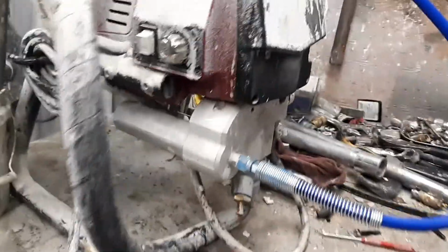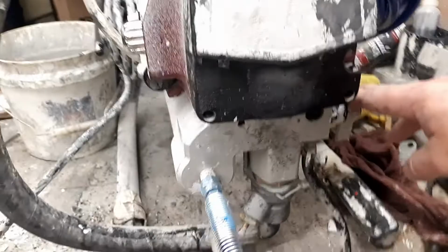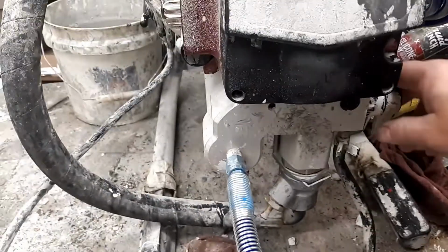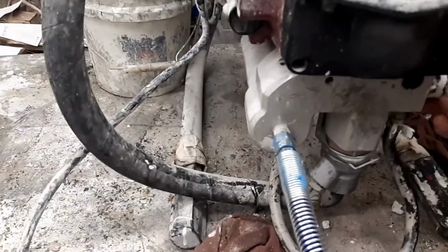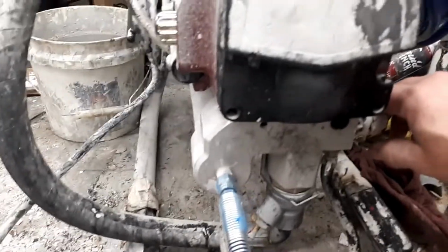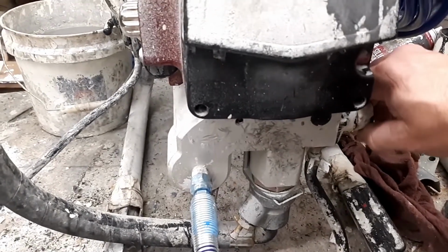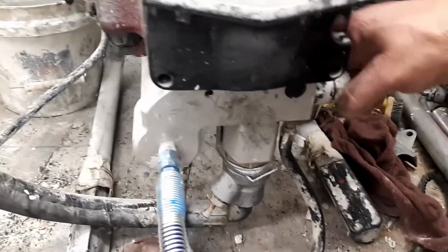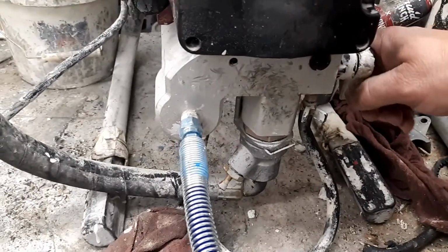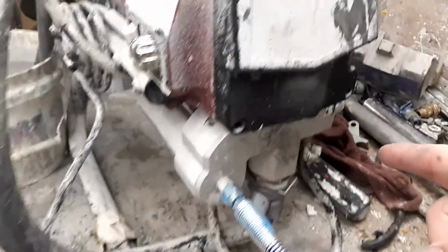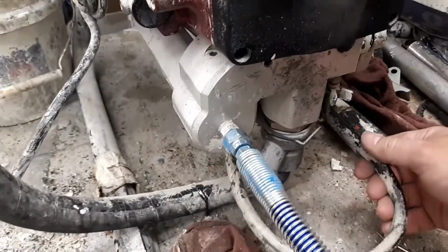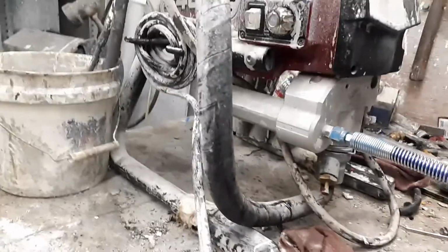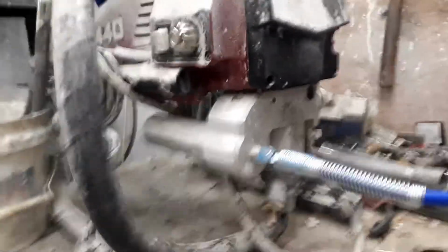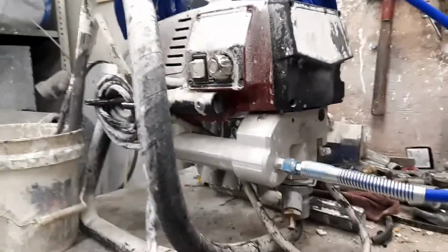I got the prime valve open, and anytime you open the prime valve on an unknown situation, always open it slowly. Don't just whip it down because you could create a mess real quick. Ease down into it to release the pressure, and you'll know at that point if it's flowing out into the bucket or building pressure in the prime hose. If you're building pressure without it dumping out, stop opening that valve, because you've got a good chance of rupturing that prime hose and creating a big mess.